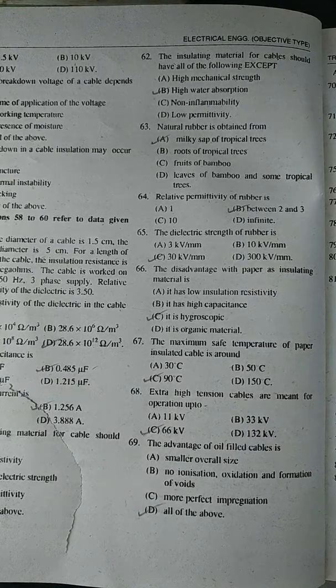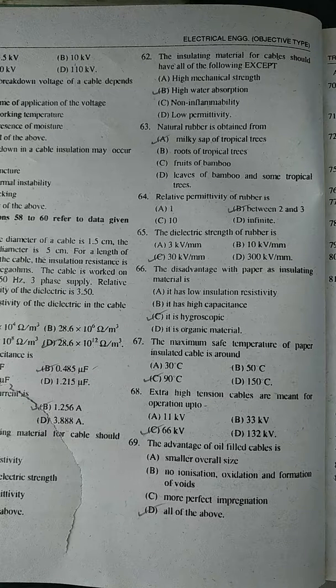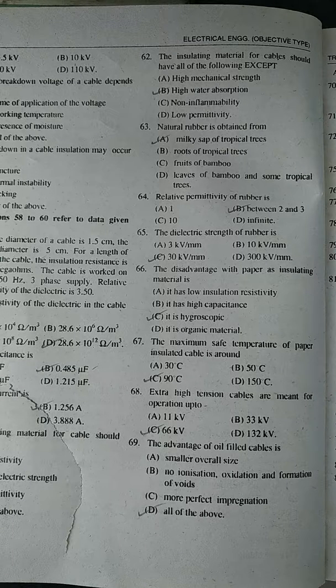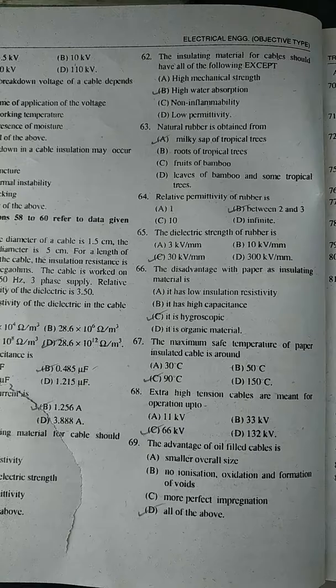66. The disadvantage with paper as an insulating material is that it is hygroscopic. The maximum safe temperature of paper insulated cable is around 90 degrees centigrade. Extra high-tension cables are meant for operation up to 66 kilovolts.